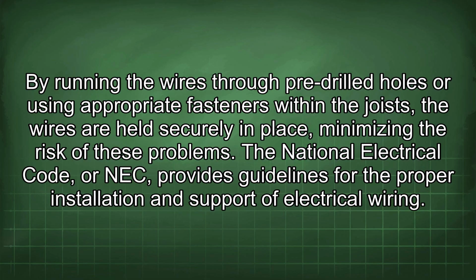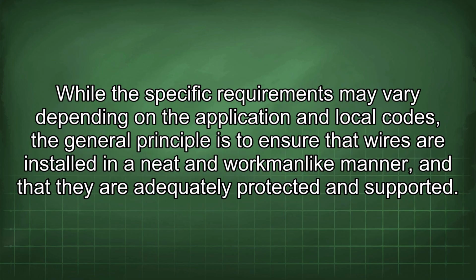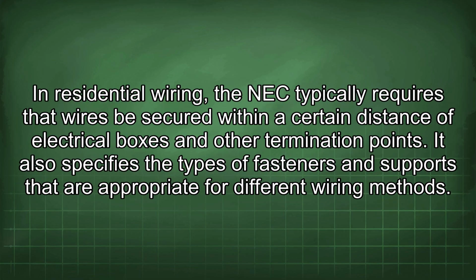The National Electrical Code, or NEC, provides guidelines for the proper installation and support of electrical wiring. While the specific requirements may vary depending on the application and local codes, the general principle is to ensure that wires are installed in a neat and workmanlike manner and that they are adequately protected and supported. In residential wiring, the NEC typically requires that wires be secured within a certain distance of electrical boxes and other termination points. It also specifies the types of fasteners and supports that are appropriate for different wiring methods.